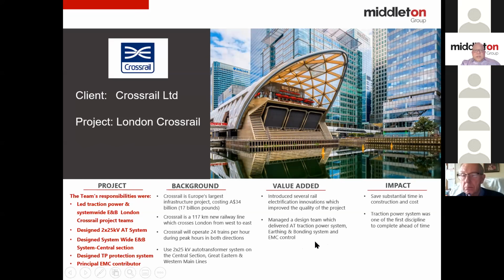And other systems, such as the earthing system, we're using the station foundation vertical bars as earth rods to create the earthing system. And because it's AC and it doesn't have the corrosive effects of DC, we were able to do that. So these are just some of the innovations.